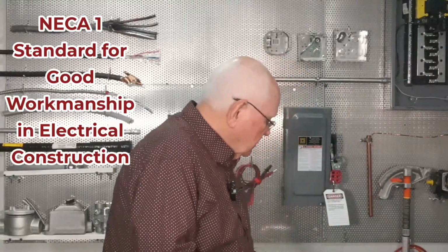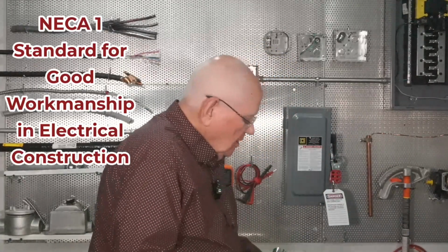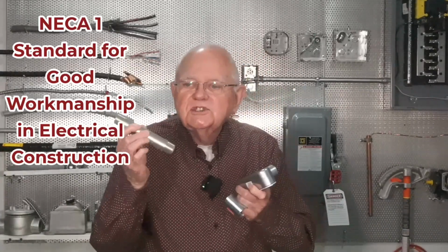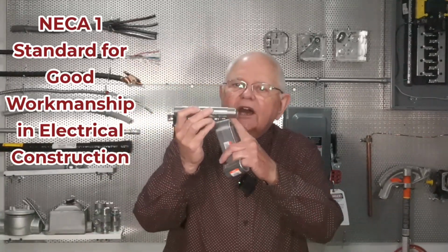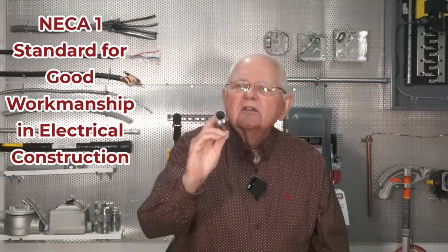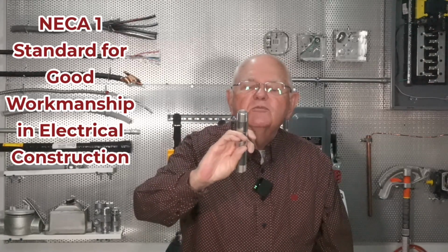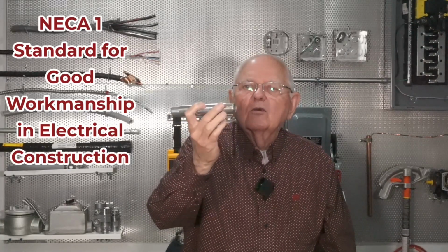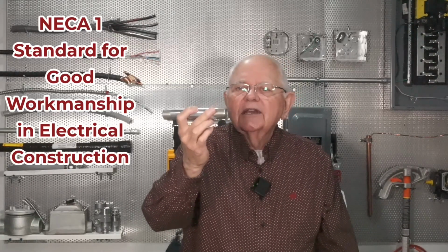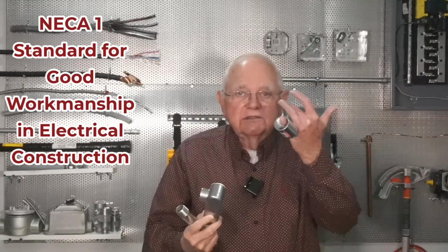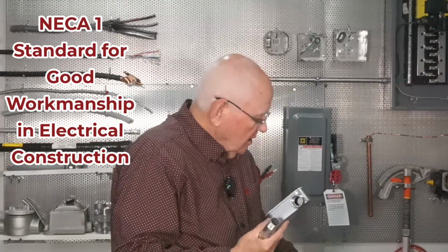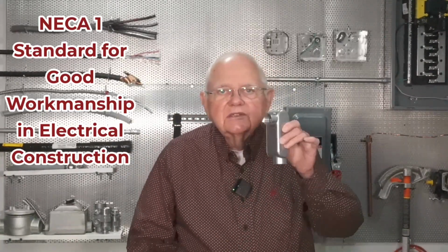So for instance, if I take some conduit here, I've got some rigid conduit. It's threaded on the end. Those are NPT threads, National Pipe Threads. They are tapered 3/4 inch per foot. If I take those threads and now I've got an LB, same thing would be with a coupling, but there are straight threads inside of this LB.